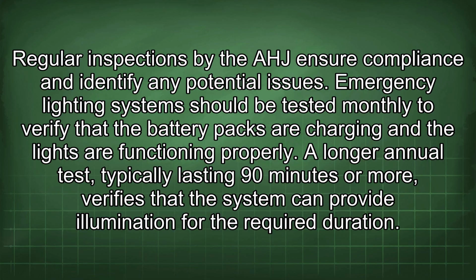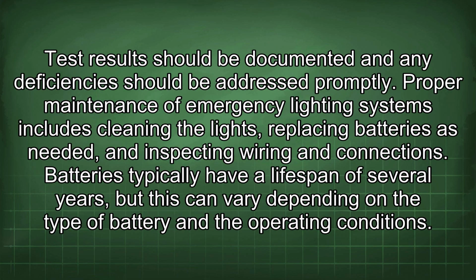Emergency lighting systems should be tested monthly to verify that the battery packs are charging and the lights are functioning properly. A longer annual test, typically lasting 90 minutes or more, verifies that the system can provide illumination for the required duration. Test results should be documented and any deficiencies should be addressed promptly. Proper maintenance of emergency lighting systems includes cleaning the lights, replacing batteries as needed, and inspecting wiring and connections. Batteries typically have a lifespan of several years, but this can vary depending on the type of battery and the operating conditions.